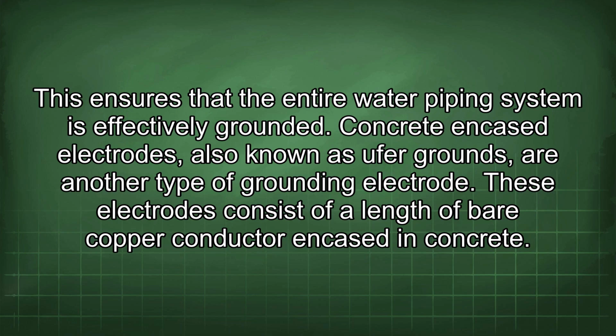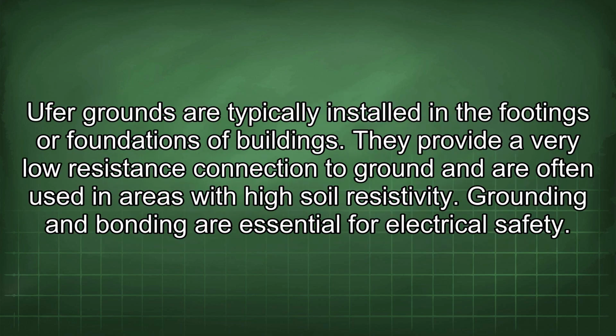Concrete encased electrodes, also known as ufer grounds, are another type of grounding electrode. These electrodes consist of a length of bare copper conductor encased in concrete. ufer grounds are typically installed in the footings or foundations of buildings. They provide a very low resistance connection to ground and are often used in areas with high soil resistivity.